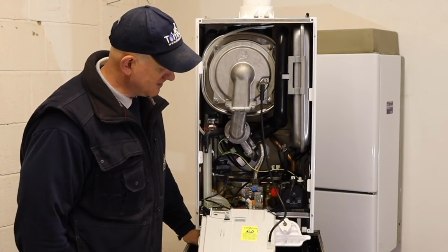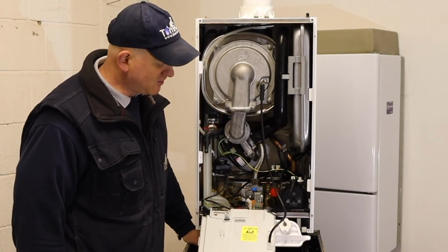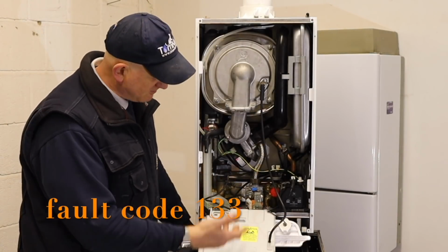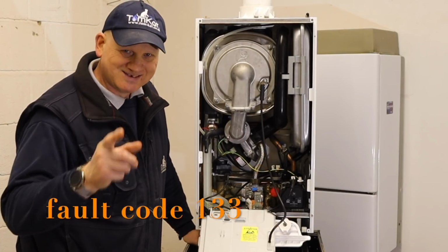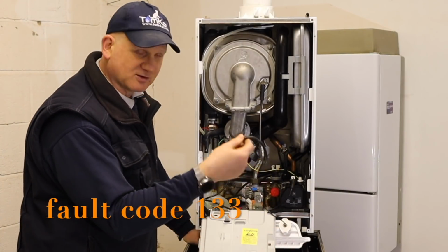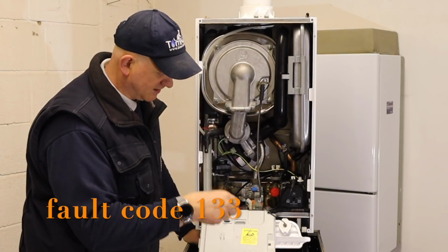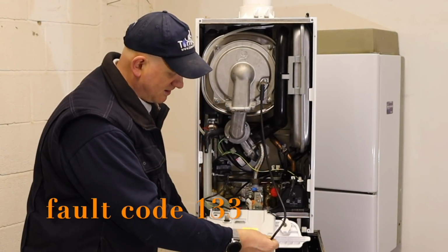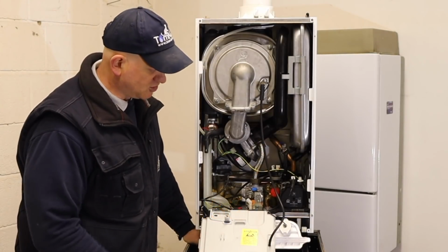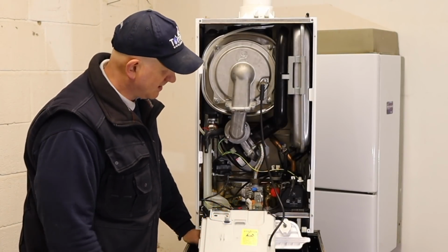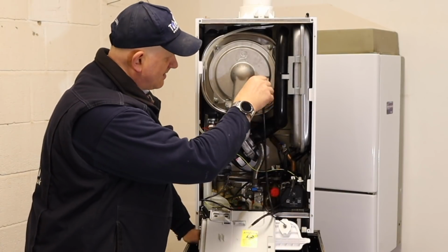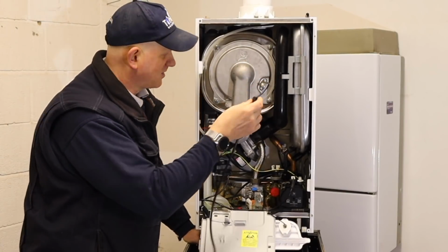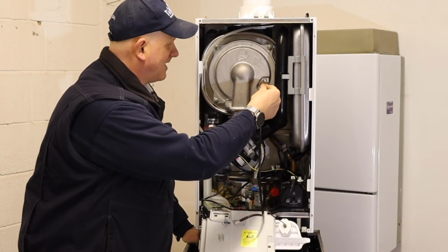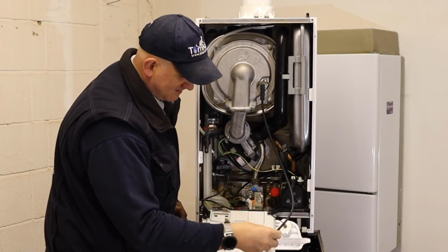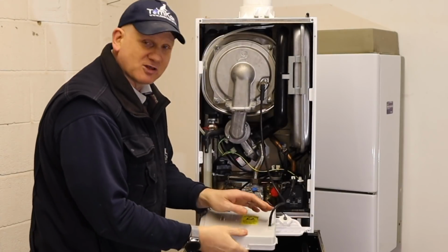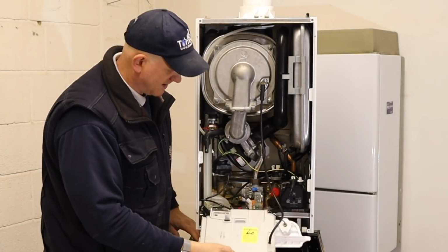Now, another fault code. If you get 133 when you've just taken the cover down, drop the flap and move it back up again, one of the things it could be is this could have fallen out, the spark electrode lead, so the HT lead. So if you do get that fault on the front of your boiler, once you've taken the cover off and dropped the flap down, it could have either come down from there or come off there. So just be aware of that. It comes off dead easy, I've found, while I've been dropping the flap down.